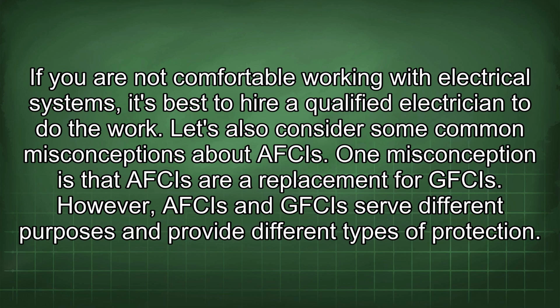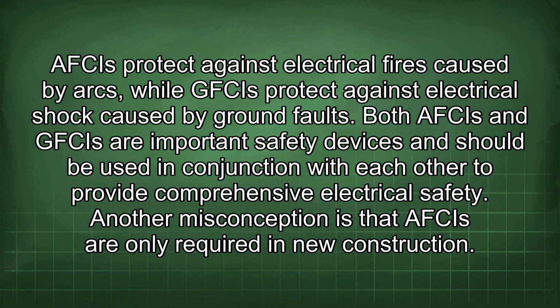One misconception is that AFCIs are a replacement for GFCIs. However, AFCIs and GFCIs serve different purposes and provide different types of protection. AFCIs protect against electrical fires caused by arcs, while GFCIs protect against electrical shock caused by ground faults. Both AFCIs and GFCIs are important safety devices and should be used in conjunction with each other to provide comprehensive electrical safety. Another misconception is that AFCIs are only required in new construction.